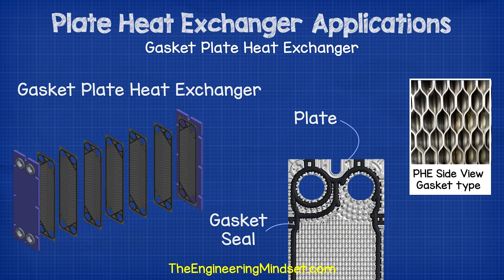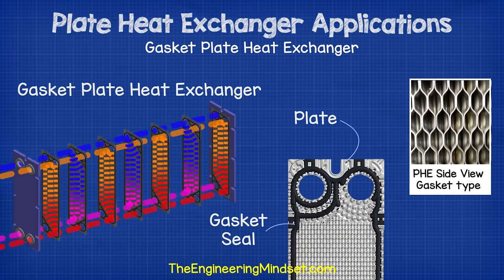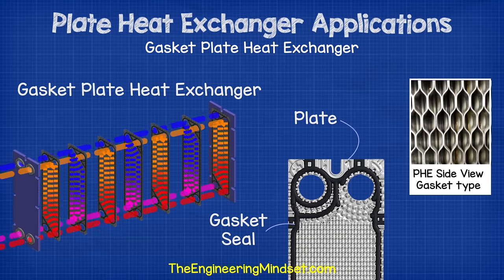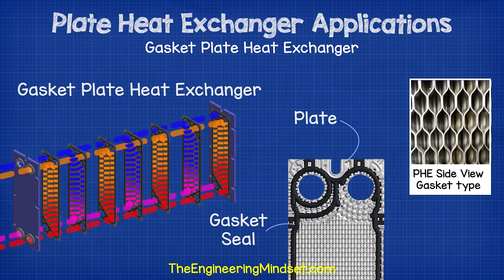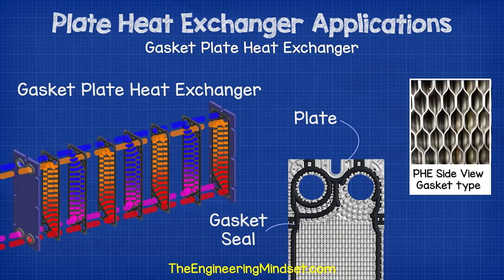Gasket type heat exchangers consist of multiple sheets of thin metal arranged to create channels. The gaskets sit between each of the plates and form a seal, preventing the fluids from mixing and leaking, and they dictate which channels each fluid can flow through. Gasket plate heat exchangers can increase or decrease their heating or cooling capacity by adding or removing internal plates, and they can also be dismantled for cleaning and maintenance. The plates are typically made from stainless steel, sometimes titanium, the end plates are usually mild steel, and the gaskets are usually made from rubber.